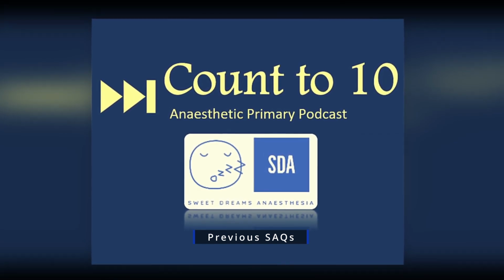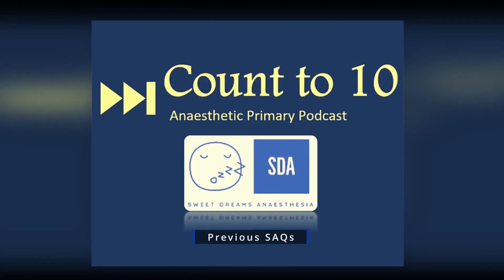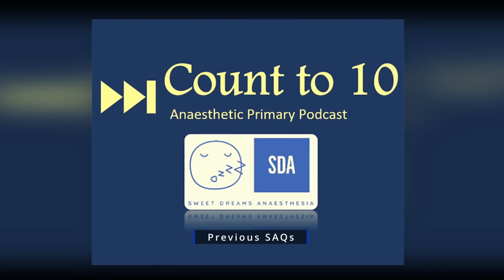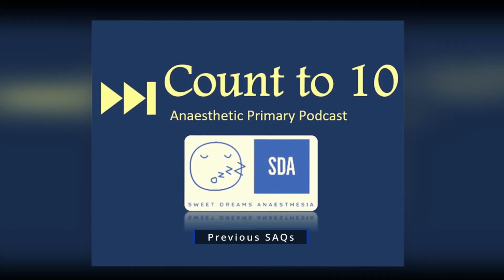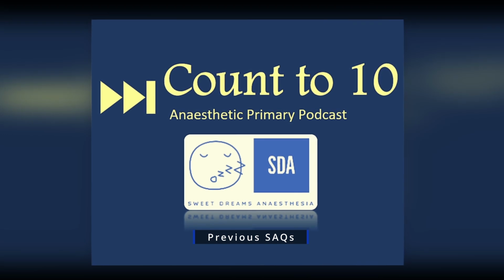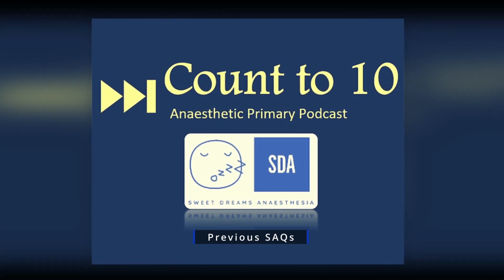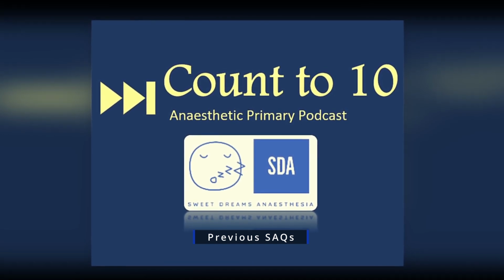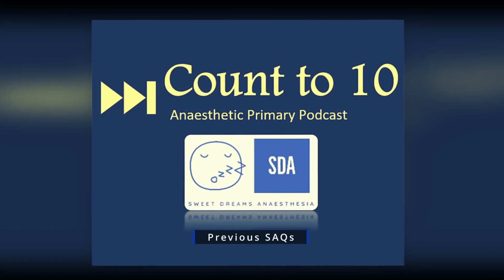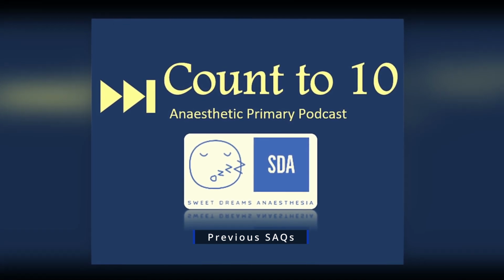In contrast with entropy, it's not really doing those time domain analyses. It's mainly looking at the frequency domain analysis. Because it's in its name, it's looking at whether there's chaos or some kind of pattern. Either way, to achieve that frequency domain analysis, it still needs to go through a Fourier transformation of that raw frontal EEG and break that EEG into multiple sine waves so that then it can analyze it.